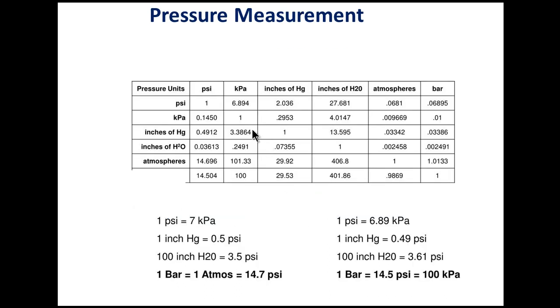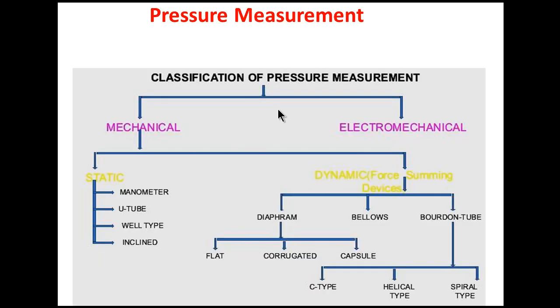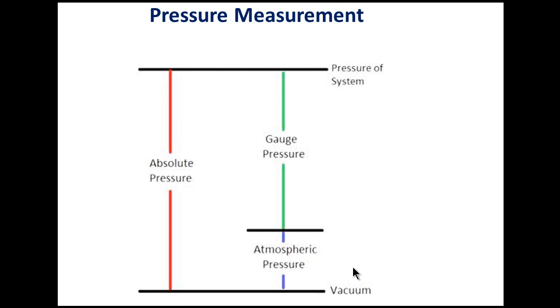Pressure measurement: pressure is defined as force per unit area. Unit conversions: 1 psi = 7 kPa; 1 atmospheric pressure = 14.7 psi; 1 bar = 14.5 psi = 100 kPa. Vacuum pressure is pressure below atmospheric pressure. Absolute pressure = gauge pressure + atmospheric pressure.